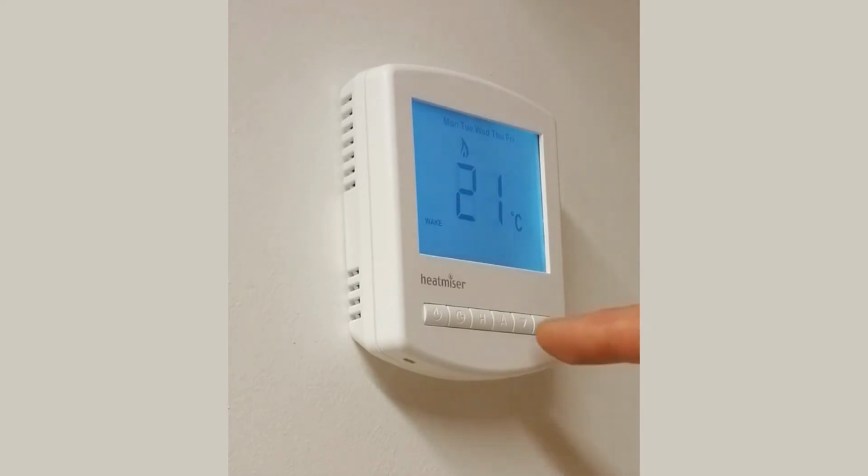Now for a heat pump it takes a long time to increase the temperature in a house. We allow about 1 degree per hour. So we would normally set this to maybe 4 or 5 o'clock in the morning so that the heat pump can start warming the house before you get up. So let's say set it to 4:30 in the morning. We now press the H to accept that and move over to the temperature.